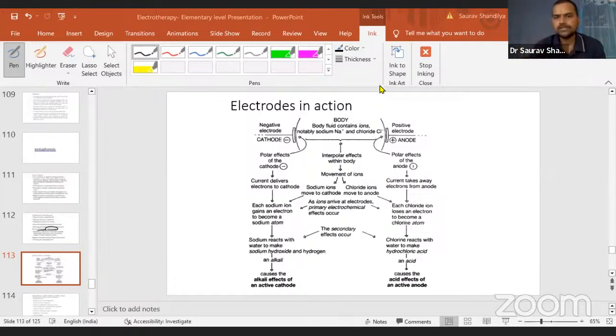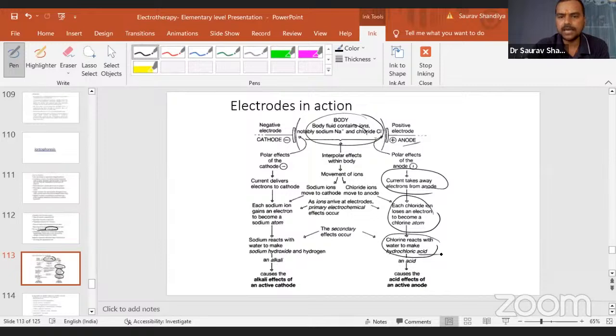So body fluid contains ions. Here we see how it works, you can check. Body fluids normally contain ions, mostly sodium and chloride. If it is a positive electrode, the polar effect of the anode is that current takes away the electron from the anode. Each chloride ion loses an electron to become a chlorine atom, and chlorine reacts with water to make hydrochloric acid. That is the acid effect of the active electrode, and that is the reason for it.